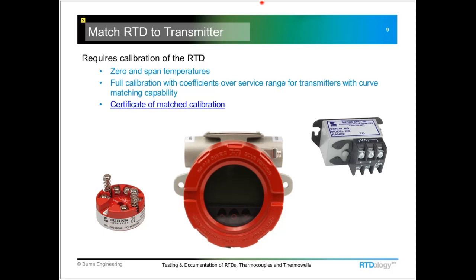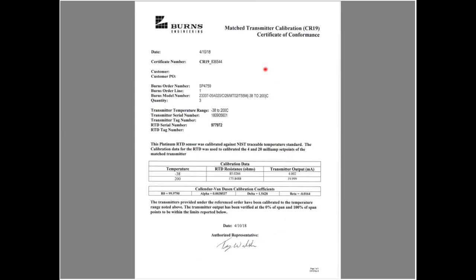So if we look at a sample certification for that, this would have some information about the probe and the order, and then farther down on this particular report there is the actual calibration data. And this one was calibrated -38 to 200 degrees C. These were the actual resistance numbers and the transmitter output. If we look here, we have the resistance at 0 degrees C. So as we can see, this one was just slightly lower than the 100 ohm nominal.